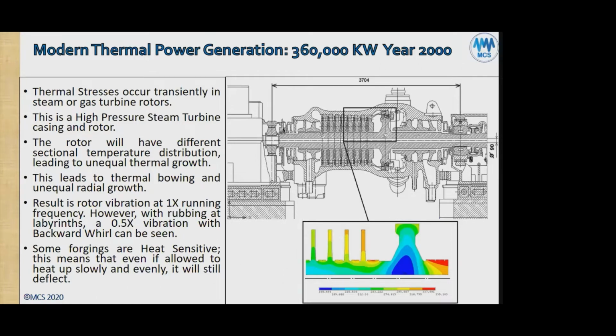As the rotor was rotating in one direction and a rub occurred, the rub causes it to slow down momentarily because it's acting like a brake. It's a metal to metal rub. So it's the rotor rubbing, for example, against the stator. And it causes a momentarily backward, just obviously it's going to keep going, but it sees it as a momentary backward rotation compared to what the normal rotation it was doing in the forward direction.